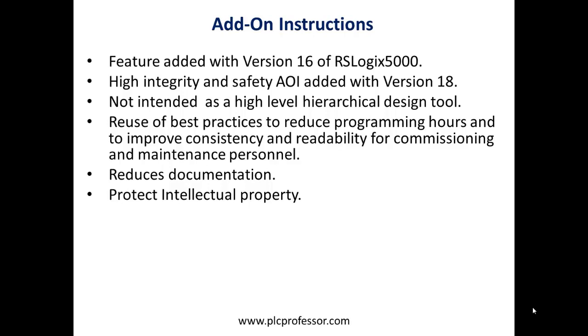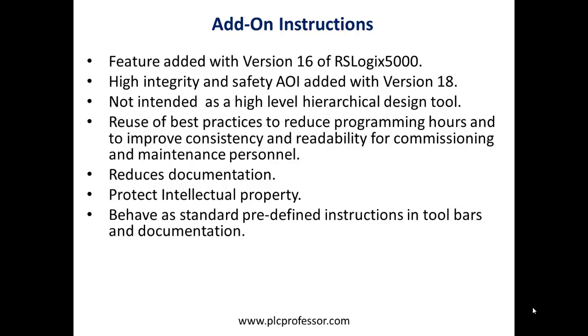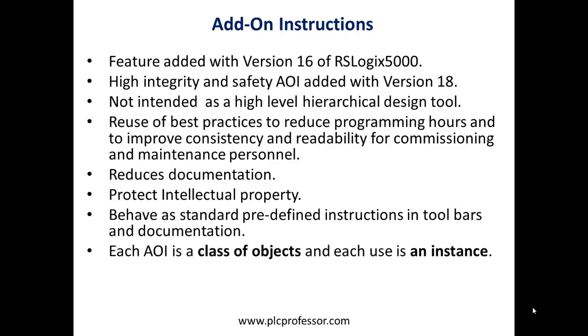Access to add-on instructions is the same as predefined instructions in both the toolbars and the help files. Once you've created and included your add-on instruction, it will show up in the toolbars and in the help files — keeping in mind that any help file content would have had to have been typed in by you. Each add-on instruction is a class of objects and each usage is an instance of that class. Each instance inherits any edits to the class, meaning that if you go back and edit the template, every instance is also updated.